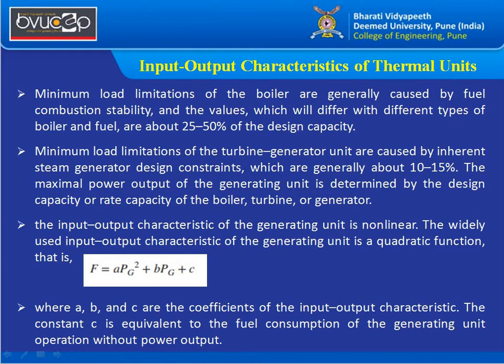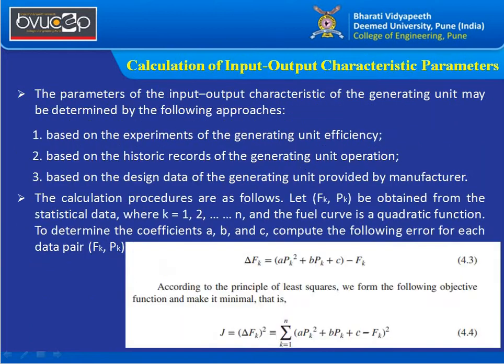The maximum power output of the generation unit is determined by the design capacity or rated capacity from the boiler, turbine, or generator. The input-output characteristics are non-linear — at every instant, power generated per unit of fuel consumed varies. The most widely used representation is the quadratic function: F = a·Pg² + b·Pg + c, where a, b, c are coefficients and c is a constant representing fuel consumption at zero power output.